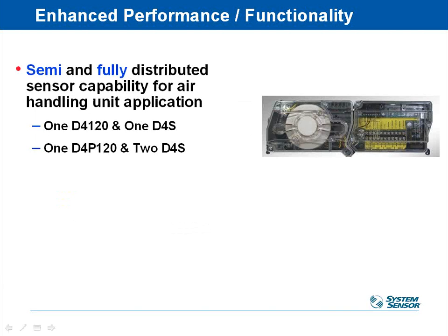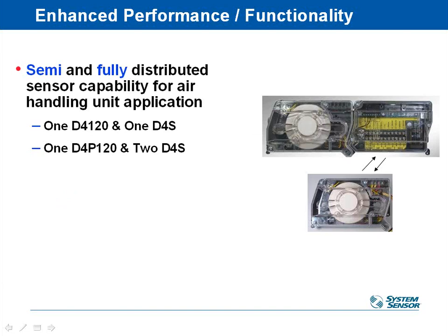All right, so there's different ways to do this. What I'm showing here is a regular detector that we would supply to you. The detector is on the left side, the electrical circuitry is on the right-hand side. You can flip it into a square or rectangular mode. However, if you need 2 detectors, one for supply, one for return, instead of buying 2 detectors and then trying to figure out how to wire them together to interlock them, you can just use the one detector and then buy just a second sensor head and wire that head back to the exact same power circuit board. So A, it saves cost because you're only buying one power and control board, but B, it also simplifies the wiring. So mount this one on the return or the supply and mount the other on the other duct.